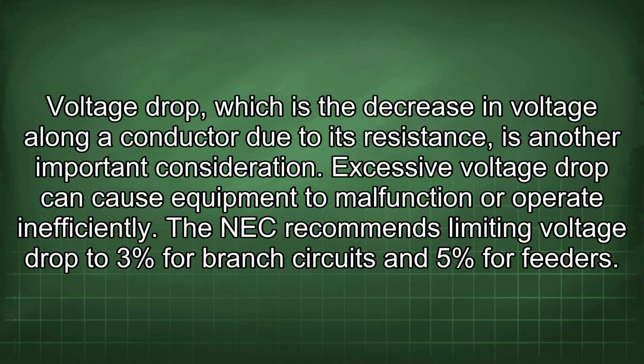Voltage drop, which is the decrease in voltage along a conductor due to its resistance, is another important consideration. Excessive voltage drop can cause equipment to malfunction or operate inefficiently. The NEC recommends limiting voltage drop to 3% for branch circuits and 5% for feeders.